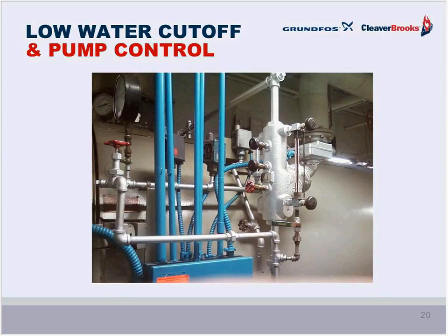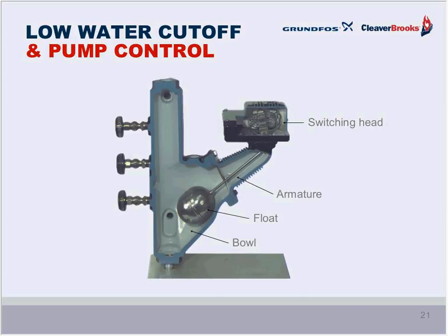Many of you, I'm sure, have seen it many times. It's the old standby, the McDonnell-Miller low water cutoff and pump control, which was a standard in the industry for many, many years and is still used quite extensively today. Now, if we look at the cutaway, you'll see the construction, including the float bowl, which contains the boiler water, and a float connected to the armature, which is connected to the switching head.